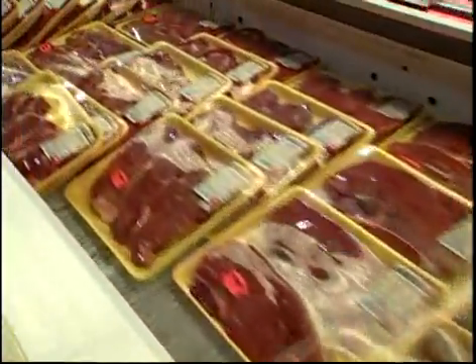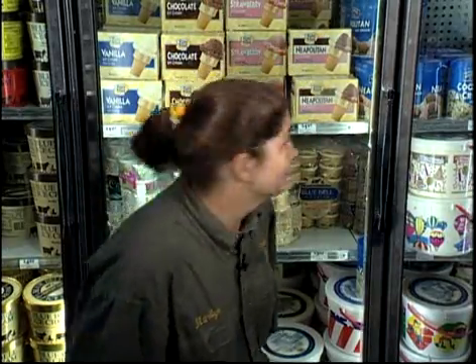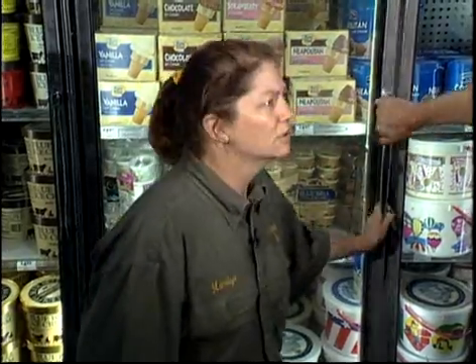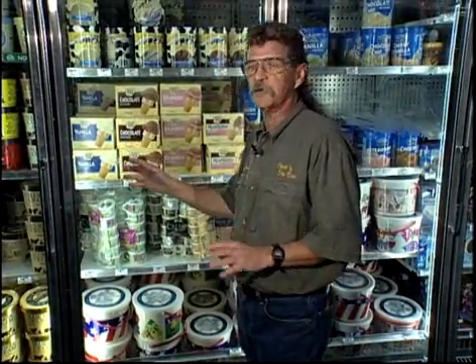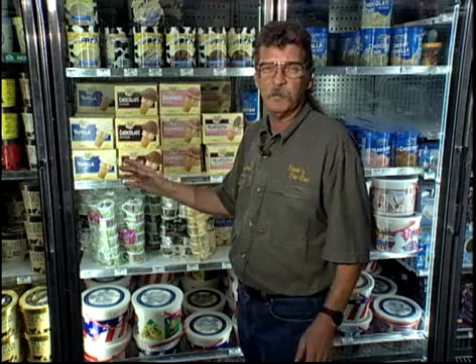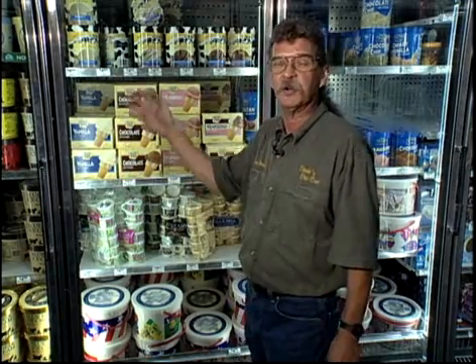These cases are considered to be low temp units. They're kept at a variety of temperatures depending on their size and whether they're horizontal or vertical. These closed door cases differ from the open ones only in that they run a little warmer — about minus five degrees. Except for ice cream. Ice cream cases need to be kept at about minus 12 degrees for a closed door case, or minus 24 for an open case. Either way, they still use the same curtain of air concept.